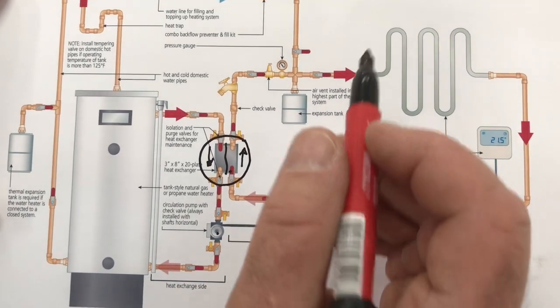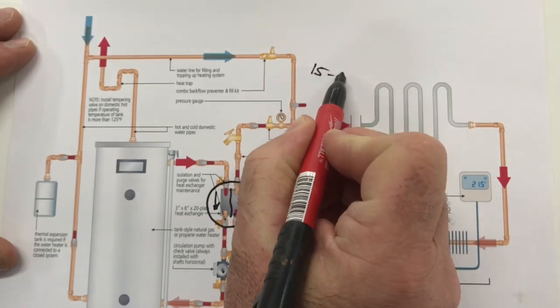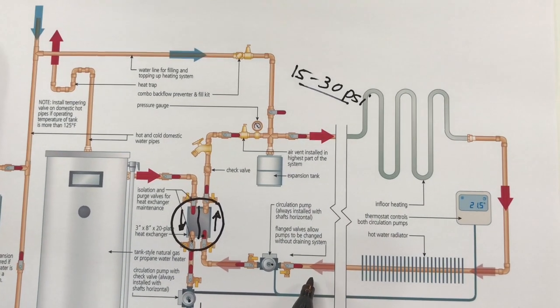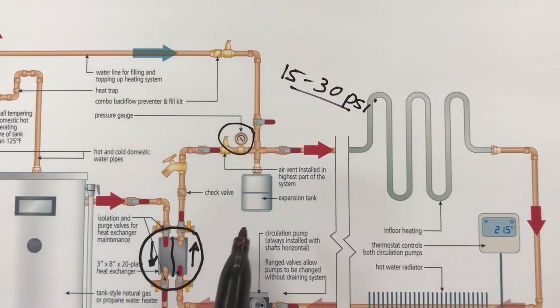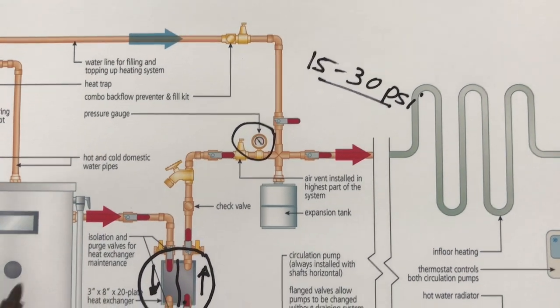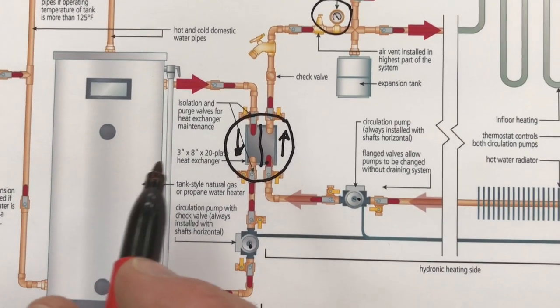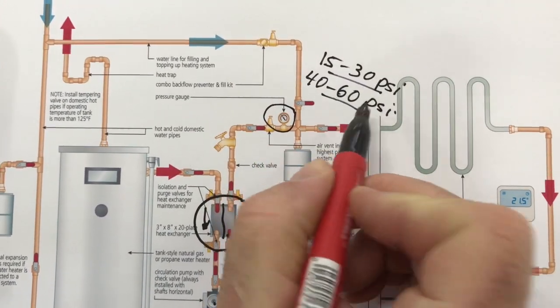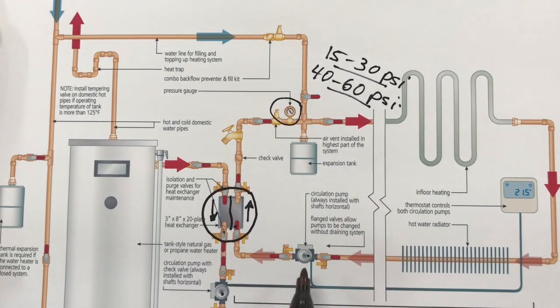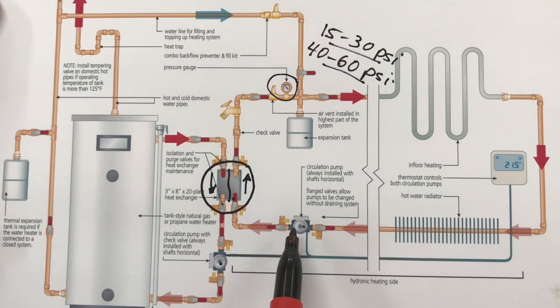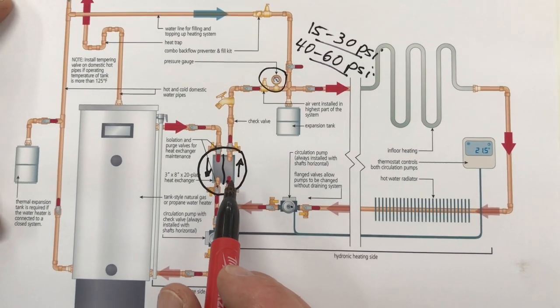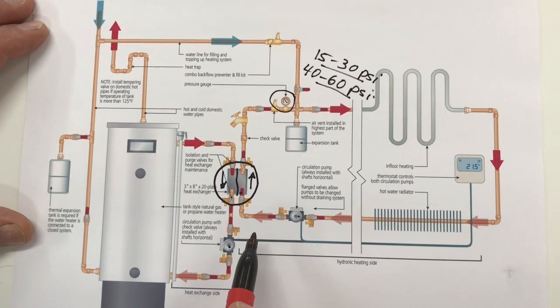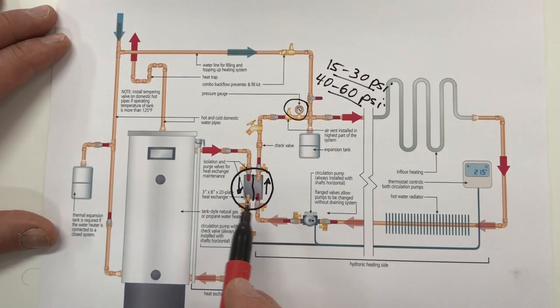Now typically the optimal pressure is anywhere from 15 to 30 psi, that's pressure of the hydronic system. If you have a system that's directly connected to the water tank then you're looking at anywhere from maybe 40 to 60 psi, that's typical municipal water pressure, and that's somewhat higher than it should be for maximum pump life. It's a minor advantage to the heat exchanger system but this is what you need to do if you can't have any exchange of the two sorts of water.